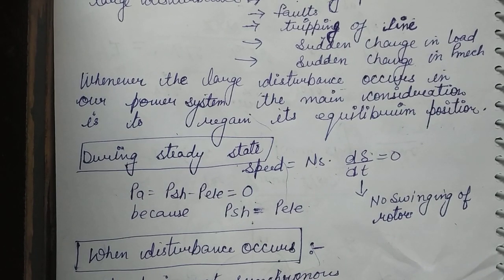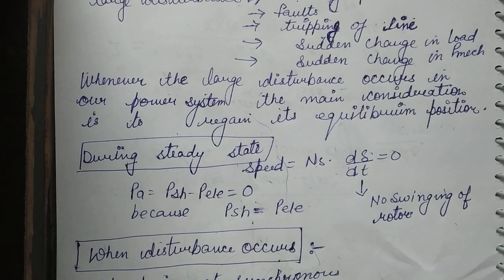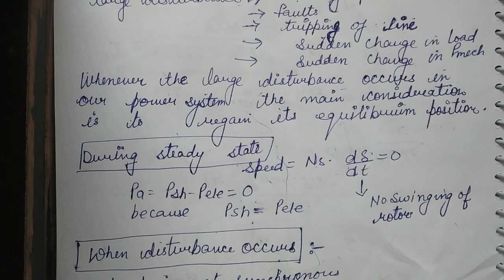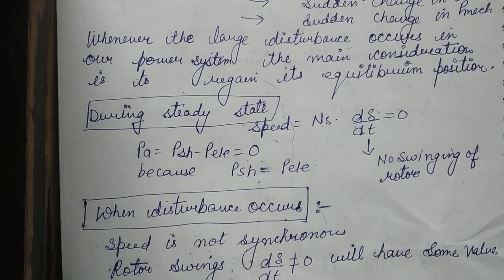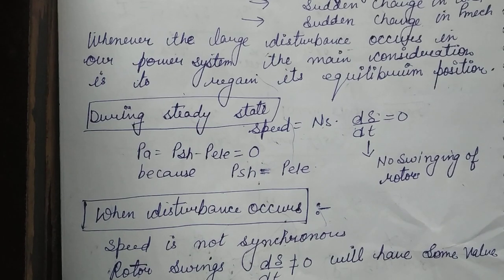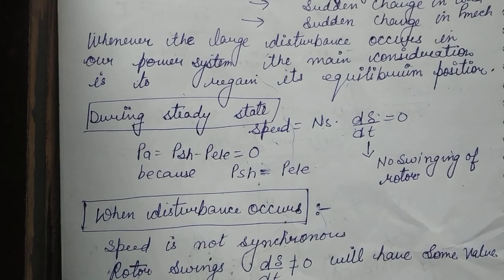For example, if the initial angle was 15 degrees, it may reach 35 degrees — so there is a large disturbance in rotor angle, large disturbance in power, and large disturbance in frequency. During that condition, it is very important that our system should not lose its synchronism. Our system is aided by fast circuit breakers and protection schemes to maintain stability.